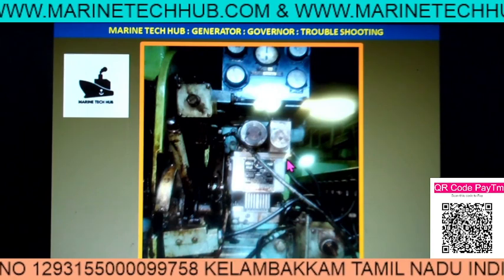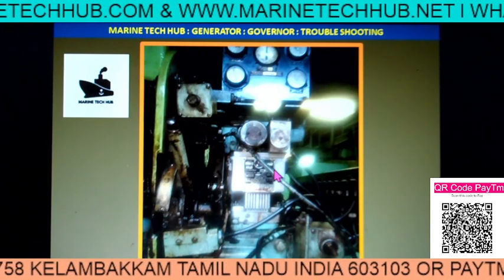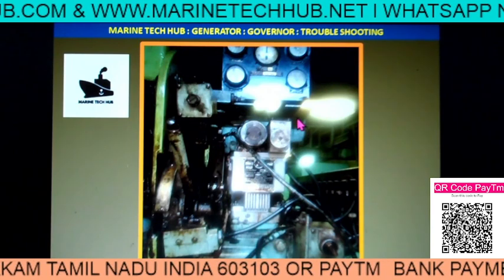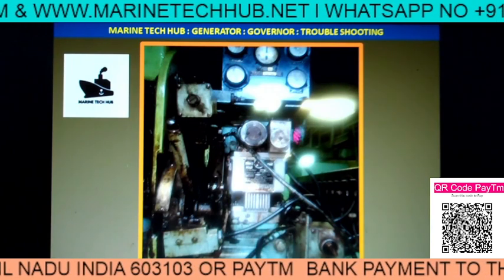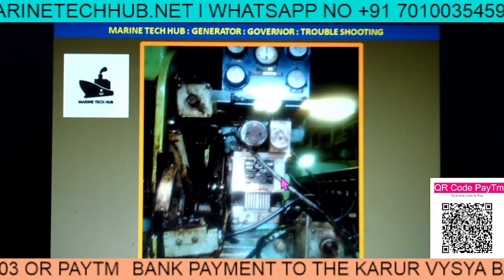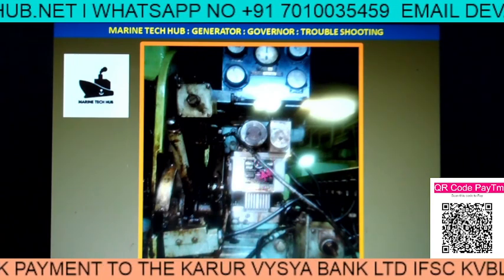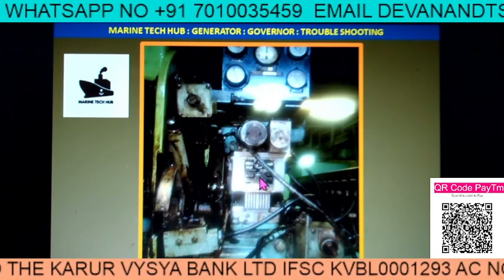We told them to change the governor oil one more time. They changed it again, but still the problem existed. So now we suspected something wrong with the governor, because the load was coming up to 200 kilowatt and after that it was not. That means when we were increasing the load, we were not able to move the governor.